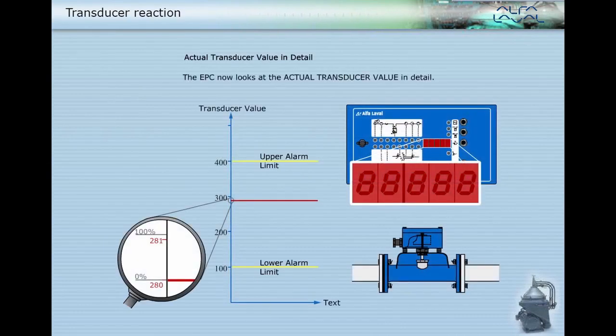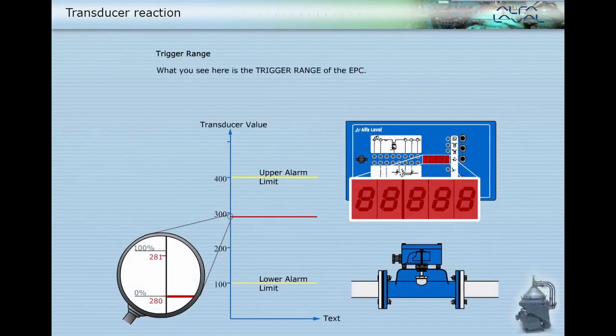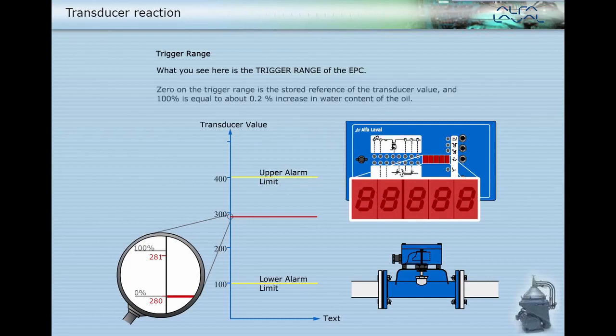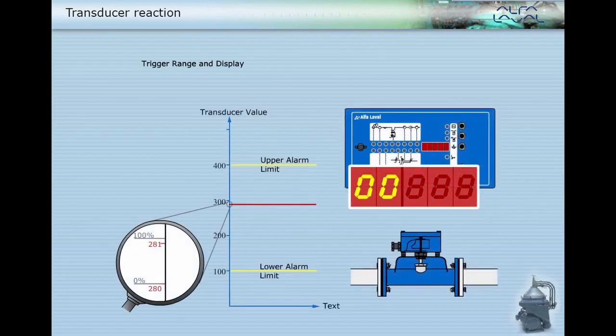The EPC now looks at the actual transducer value in detail. What you see here is the trigger range of the EPC. 0 on the trigger range is the stored reference of the transducer value. 100% is equal to about a 0.2% increase in water content of the oil. The trigger range is displayed by 0 to 100% in the left-hand side of the normal display.